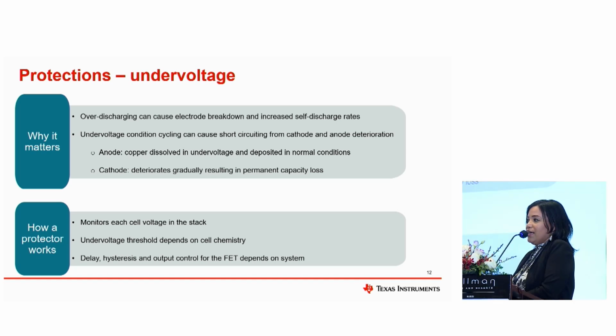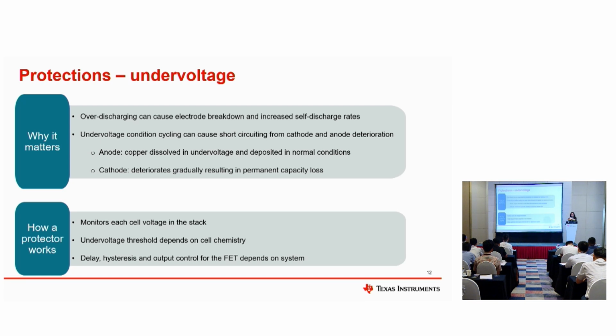Undervoltage is similar to overvoltage. A lot of people understand that lithium-ion overvoltage can damage the battery, but going extremely undervoltage can also damage the battery. So it is important to also protect your battery from going too low. If your battery consistently goes extremely depleted, it will reduce the capacity of the battery, and it could also create a short inside your battery due to the chemistry. So some of the secondary protectors, though it's not as critical as overvoltage, will also look for undervoltage on your lithium-ion battery. The mode of operation is exactly the same as overvoltage, but in the opposite direction.